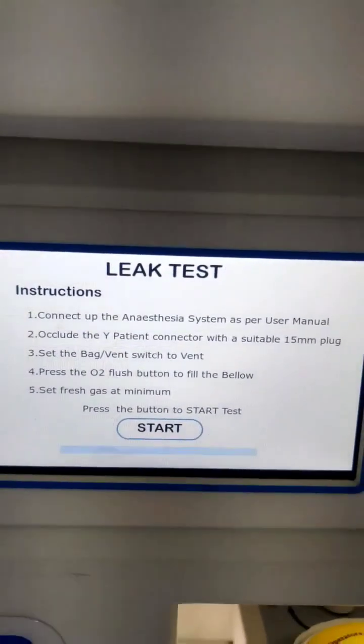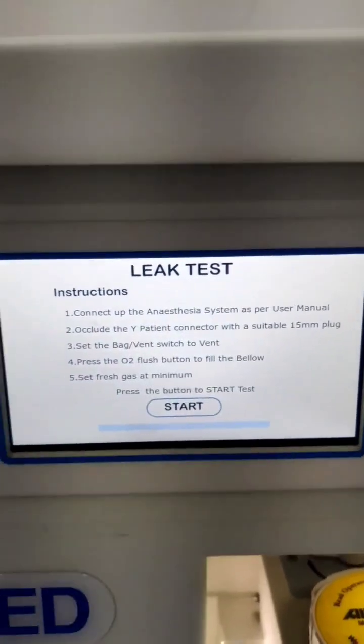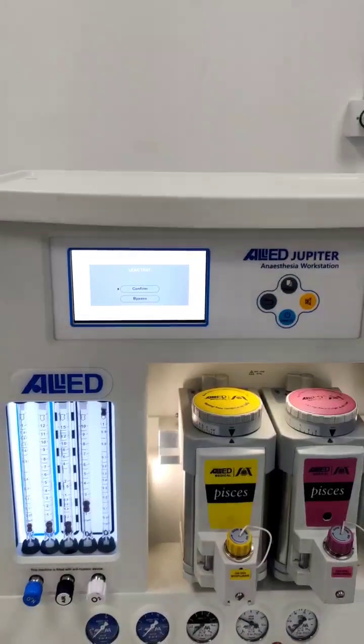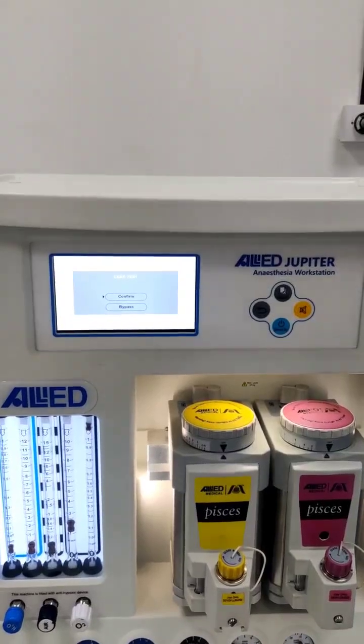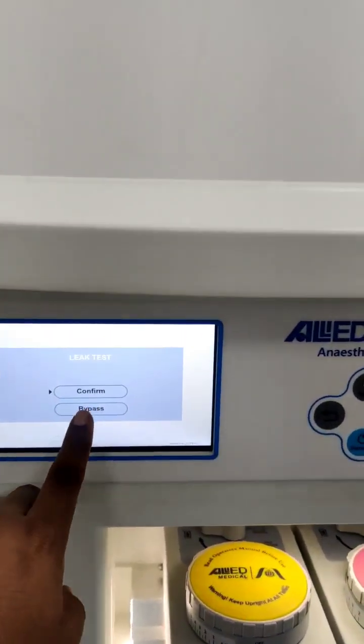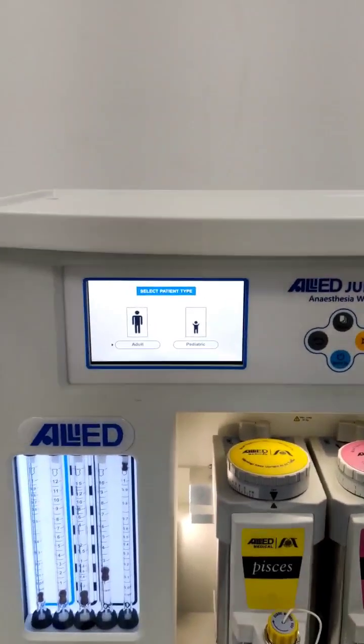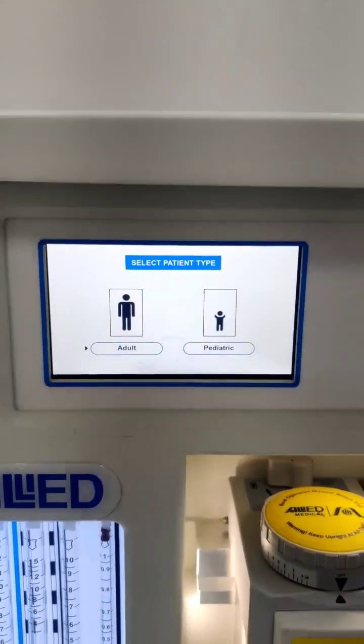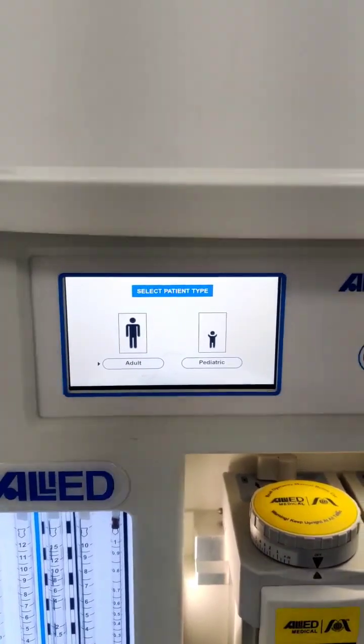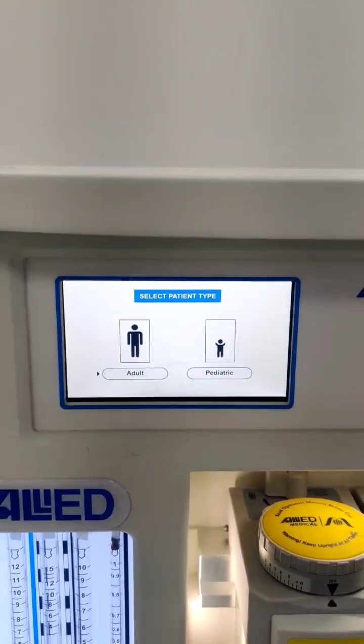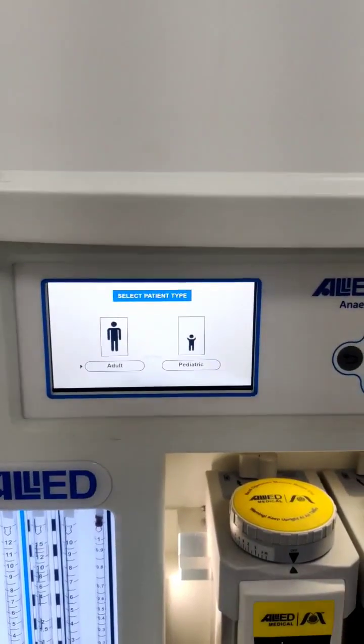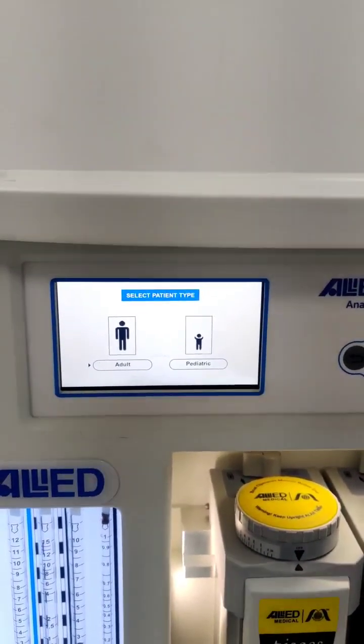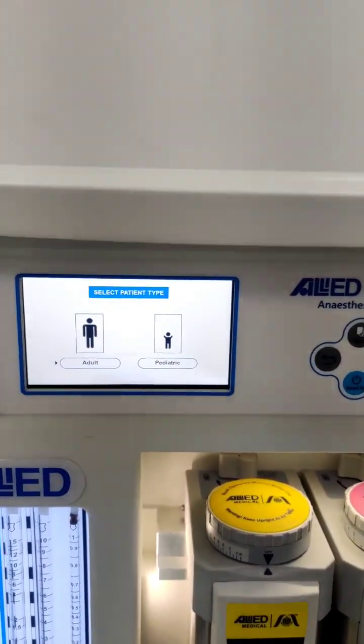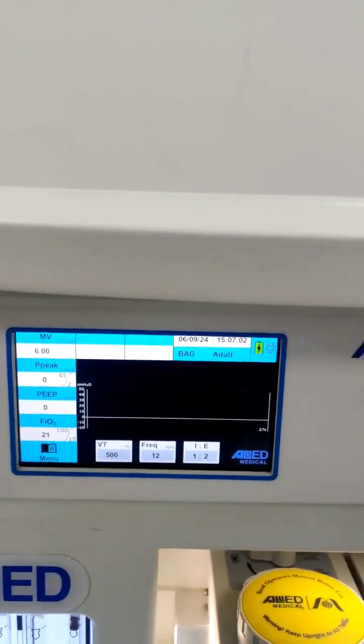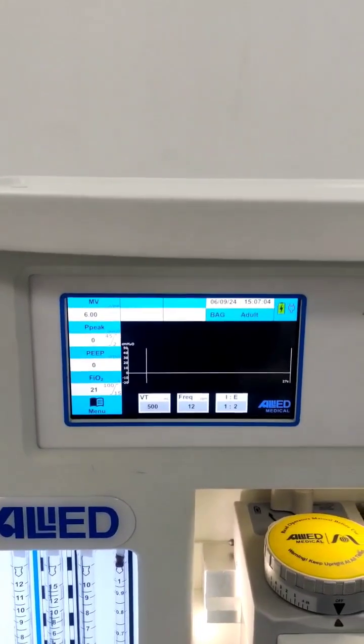For doing the leak test, these are the steps that have to be followed, and then the leak test has to be performed. For bypassing the leak test, there is an option of bypassing. You can select it from here. As soon as you bypass the leak test, you will get the option over here for selecting the patient type. We are giving two options for selecting the patient: one is the adult and the other one is the pediatric patient. In this, the tidal volume starts from 50 ml and goes up to 1500 ml. Now after selection of the patient, you will get the standby user interface.